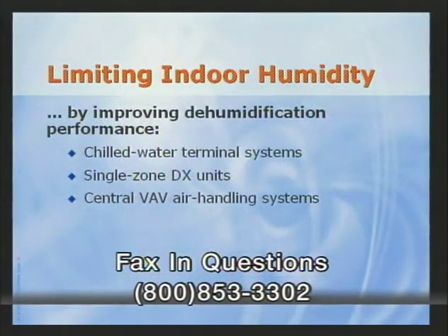Now, one word that you kept using before was basic constant volume system. What's being done with constant volume systems to address the higher density of people and humidity levels and the more humid locations? Well, in the next section of the broadcast, we're going to look at three common types of HVAC systems that are used in schools and some methods for improving their dehumidification performance. The first two, chilled water terminal systems and single zone DX units, typically are basic constant volume systems, just like the example I shared. The third is a central VAV air handling system.